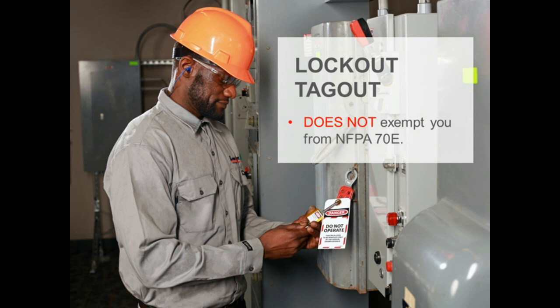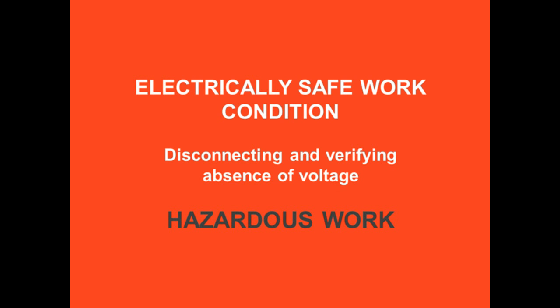That's why lockout tagout violations are still in the top 5 most cited OSHA violations every year: there's a thing in lockout tagout called verification of isolation when we're doing electrical work. We have to actually verify that the system is de-energized. And guess what? That is considered hazardous work to OSHA. That's considered live work until we have verified that the system is actually de-energized. It's still considered live work.